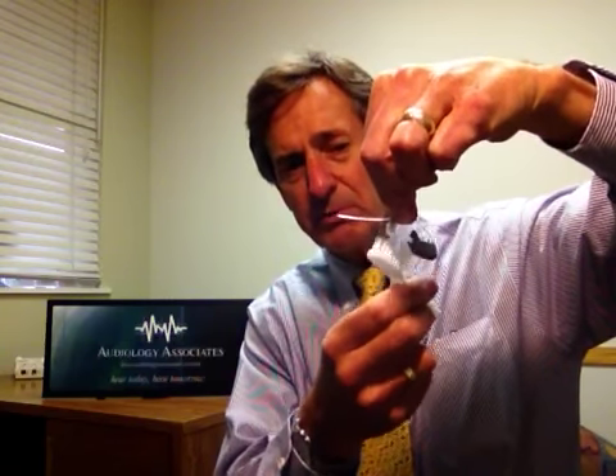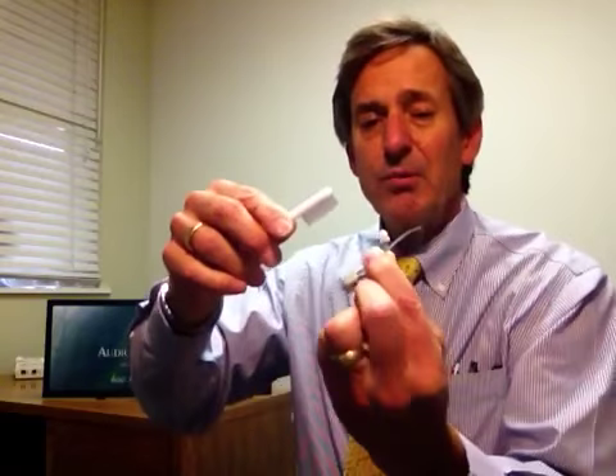And then in the morning, what you can do is there is a small case that we provide with the hearing instruments, which will have a small brush, and you would hold the speaker so it's pointing down. Simply take the brush and gently rub it over the edge of the hearing aid speaker, and you can dab it just a little bit, and that will dislodge any debris from the speaker and it will fall out and clean. This is the best way to clean the hearing aid. I don't recommend holding it with the speaker pointing up. This doesn't allow the debris to fall away from the speaker.